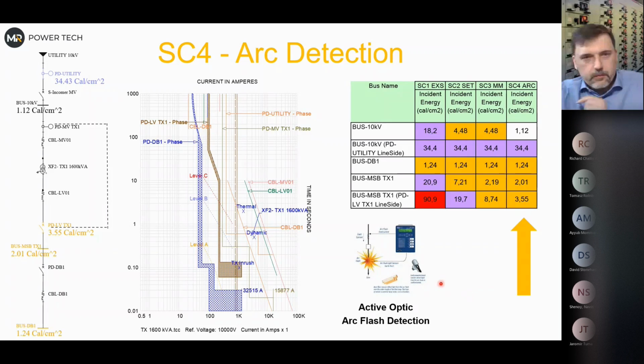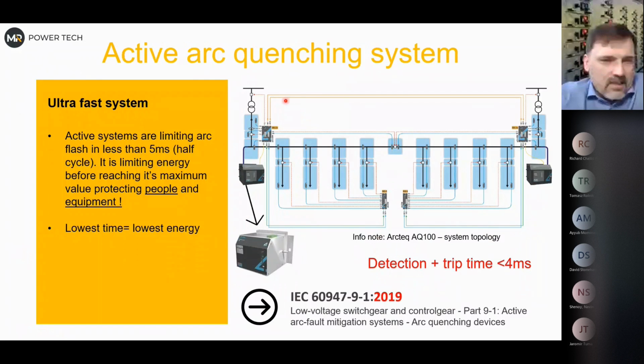What else can we do? That's, let's say, an overview of the scenarios we did for the project, but in practice, we can also extend the arc flash detection system with a quenching device. So then we have an arc flash quenching system. It's the same story, just we send a signal to the device which is called a quencher. The way it works is easier to show you, but it makes a 3-phase fault on the bus bars very fast, under 4 or 5 milliseconds, it has to be very fast. Then it creates the 3-phase fault, and in the place of the fault we have no voltage or very limited, reduced voltage, which means that the arc cannot sustain because there is no voltage in the system in this area.